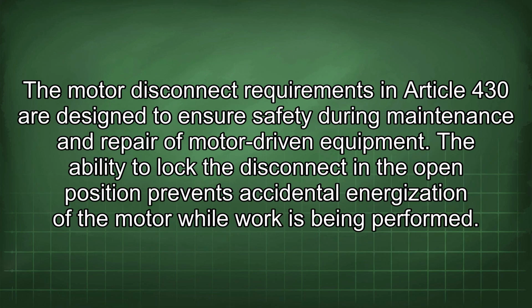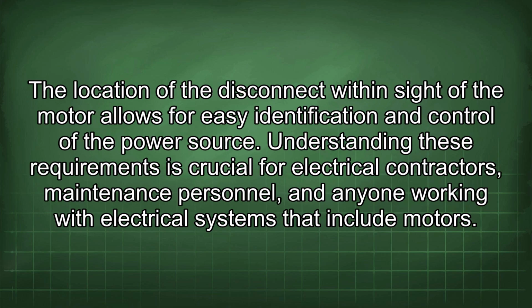The motor disconnect requirements in Article 430 are designed to ensure safety during maintenance and repair of motor-driven equipment. The ability to lock the disconnect in the open position prevents accidental energization of the motor while work is being performed. The location of the disconnect within sight of the motor allows for easy identification and control of the power source. Understanding these requirements is crucial for electrical contractors, maintenance personnel, and anyone working with electrical systems that include motors.